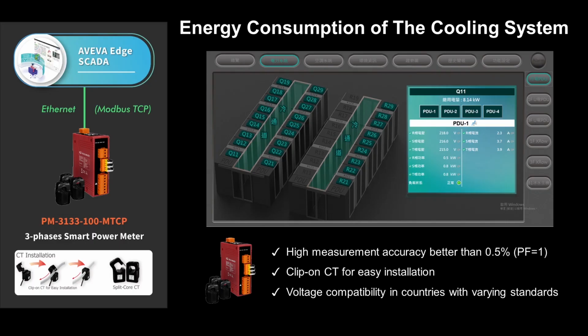To obtain the data on energy consumption of the cooling system, the client uses PM3133 100 MTCP 3-phase smart power meters for energy measurement. The smart power meter is high accuracy and is suitable for low voltage primary winding and medium or high voltage secondary winding. Users can get reliable energy consumption data and monitor equipment operation in real time. Besides, PM3133 100 MTCP provides an open CT for measurement.